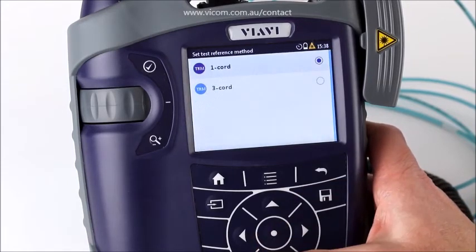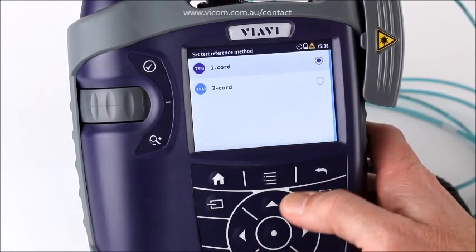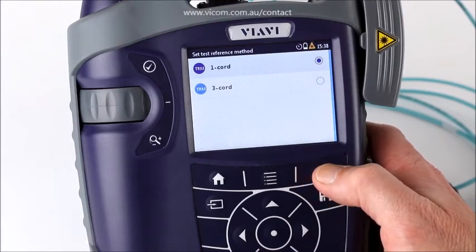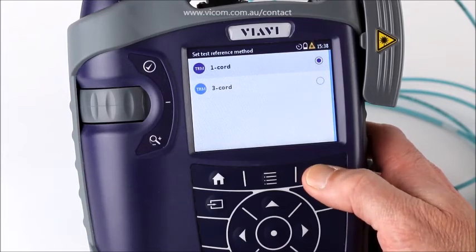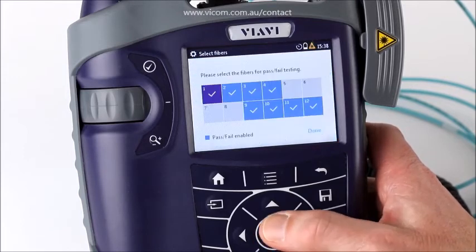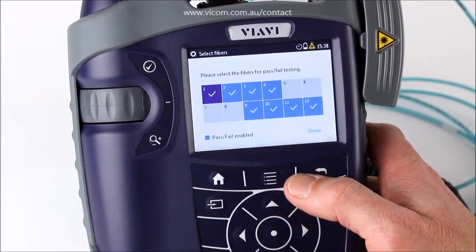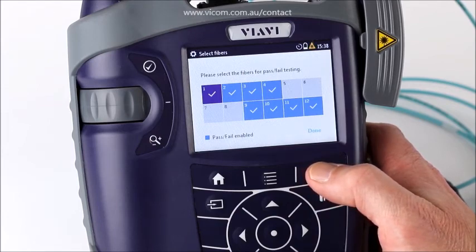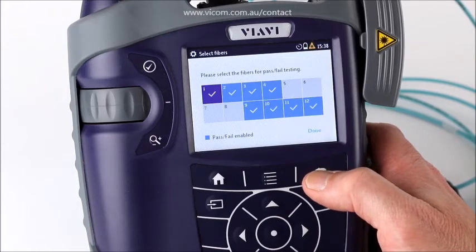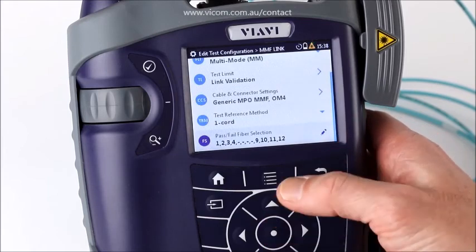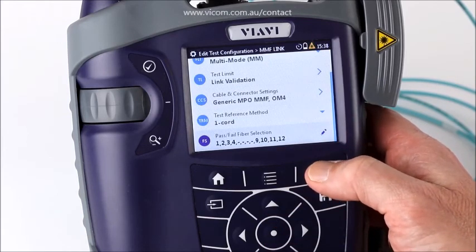The one-cord reference method is the standard one. In some cases you may need to do a three-cord, but with MPO connectors — due to pinned and unpinned ends — a two-cord reference is really not possible. You are also able to select which fibers are used for pass/fail analysis. All fibers are always measured; it's just whether excessive loss on them causes a fail. In this case I've turned off fibers five, six, seven, and eight because SR4 technology does not use those, and although I want to see their loss, I don't want them to impact my pass/fail result.